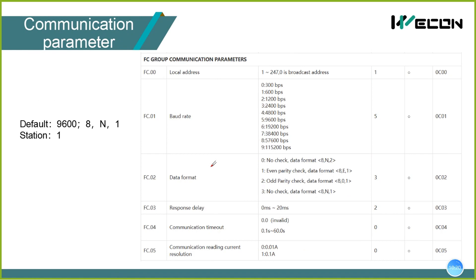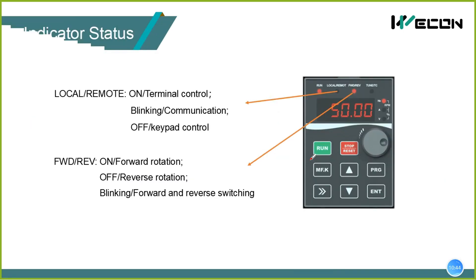Set the communication parameters in the FC group. Generally, the default parameters are OK. After this setting, when the inverter is in communication mode, you can see the LOCAL/REMOTE indicator blinking. If the indicator is off, it belongs to keyboard control.